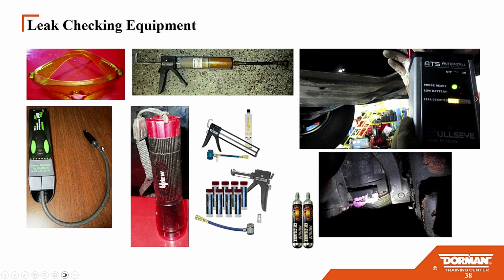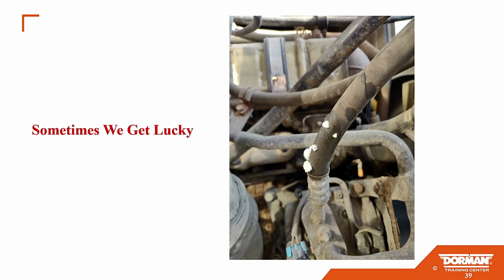For example, with the electronic type detectors you got to go very, very slow. And the refrigerant vapors are heavier than air, so usually you got to try to get it underneath the fittings and everything. So they're a little bit hard. You got to identify the leak, you can't just take it out, put some in, let it rip, and a week later it's right back. Again, it's leaking for a reason. And of course sometimes we get lucky, but you still can't beat a good visual if it's possible.